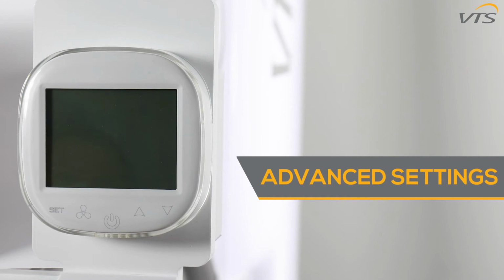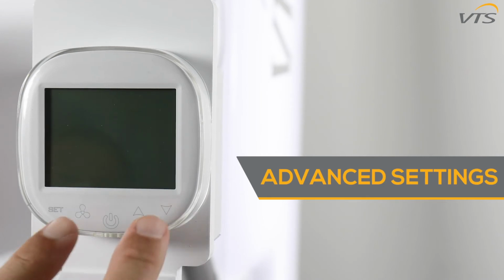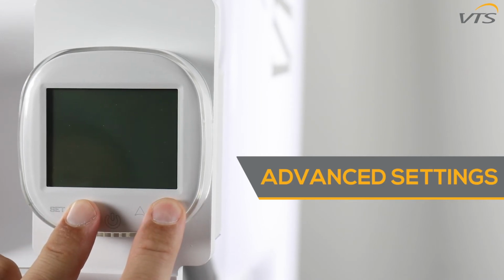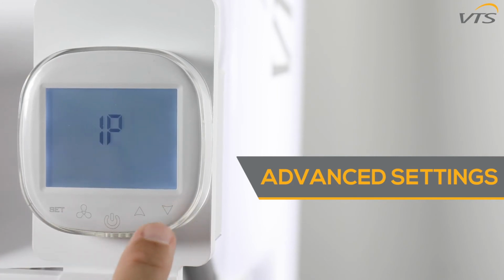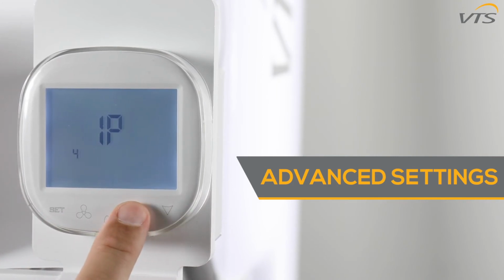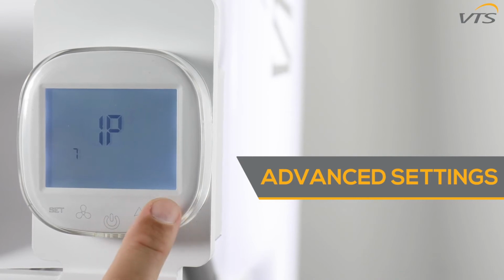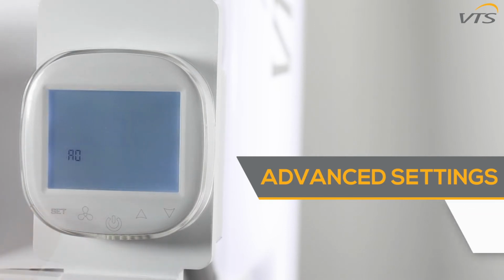Your controller must be off to activate advanced settings. Press and hold the fan and down buttons to go into advanced settings. The IP function allows you to input the correct IP numbers for your building management system. Use the up and down buttons to reach your correct number and the set button to enter the value and proceed to the next function.